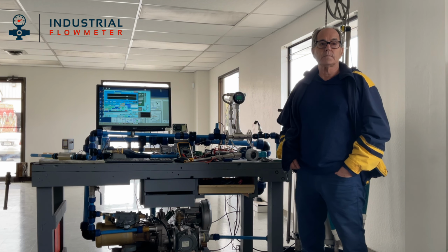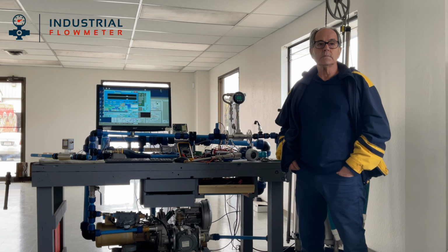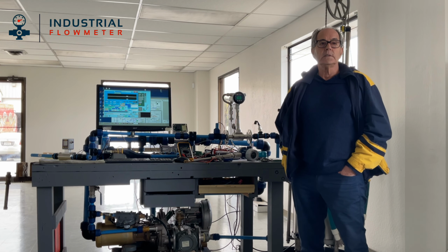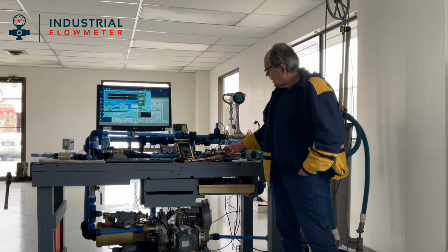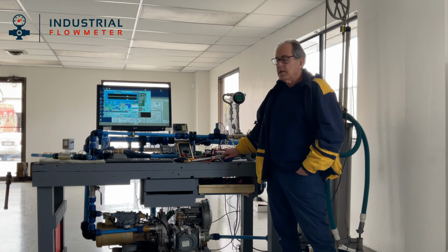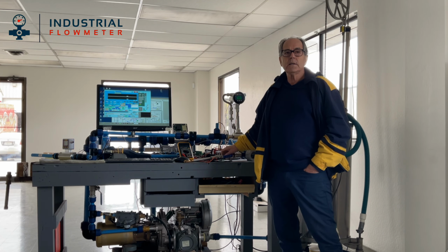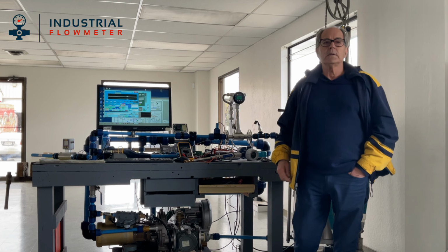And just one question, when you say time domain, I remember that anything that has an output that's frequency is in the time domain, is that right? Yes. And if something has an output that's in volts, that's the amplitude domain? I don't know what domain it's called. It doesn't matter. But by time domain, all we mean is that we have an output that's a frequency, and we're mapping a frequency to a flow rate.